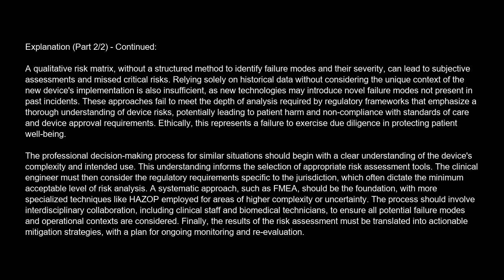The professional decision-making process for similar situations should begin with a clear understanding of the device's complexity and intended use. This understanding informs the selection of appropriate risk assessment tools. The clinical engineer must then consider the regulatory requirements specific to the jurisdiction, which often dictate the minimum acceptable level of risk analysis. A systematic approach, such as FMEA, should be the foundation, with more specialized techniques like HAZOP employed for areas of higher complexity or uncertainty.